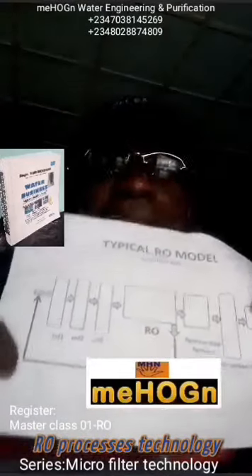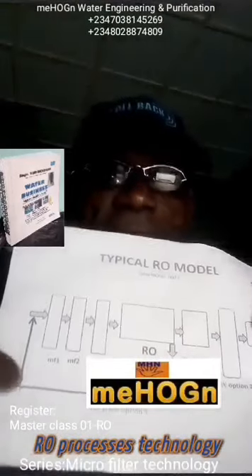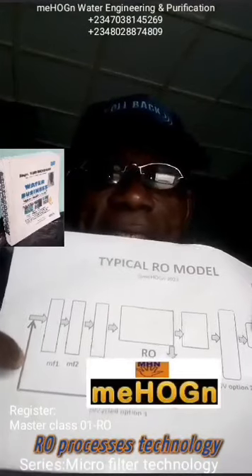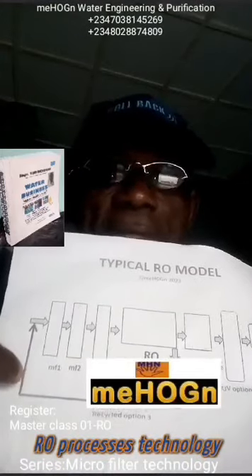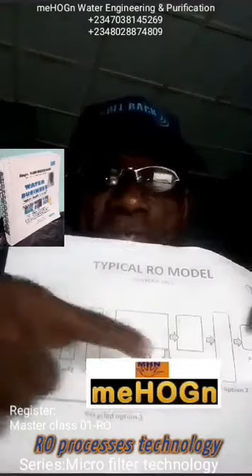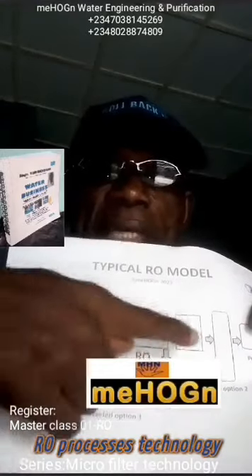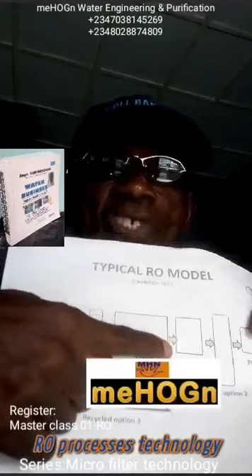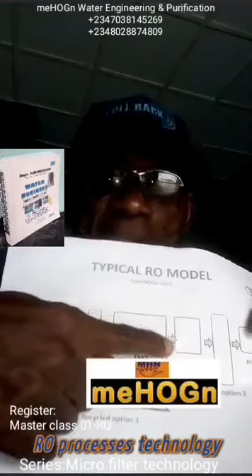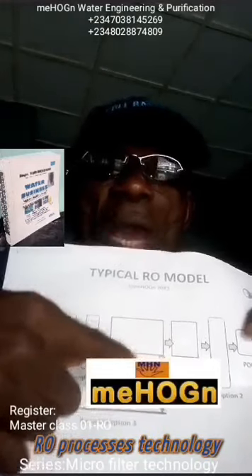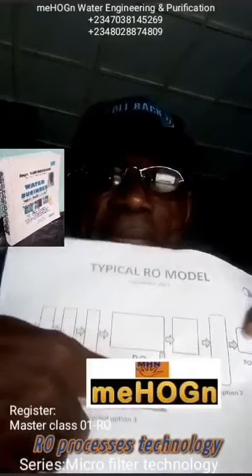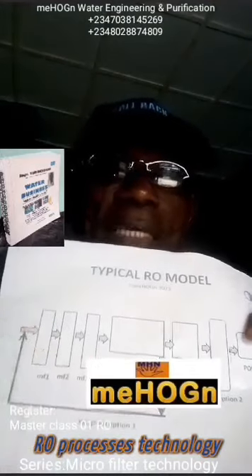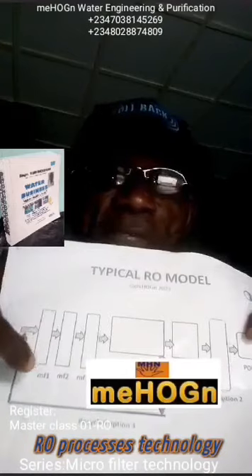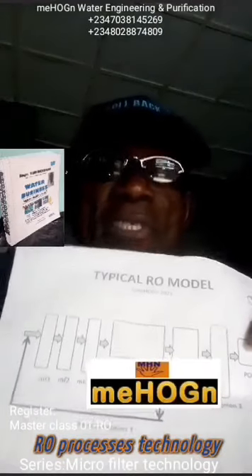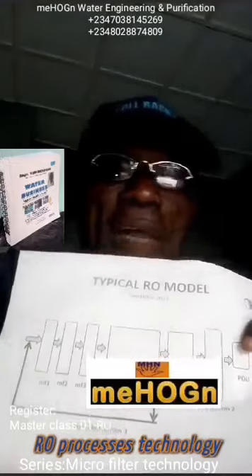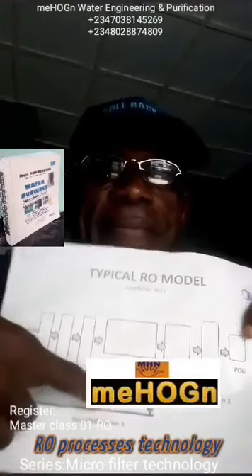This line is the line that carries the concentrate, the extracted contaminants from the RO system. So there are two outlets at the exit. This one carries the permeate, that is the treated water, while this line carries the rejected water. You can recycle this water back to the system for retreatment. So it's left for the operators of the companies based on their available resources.